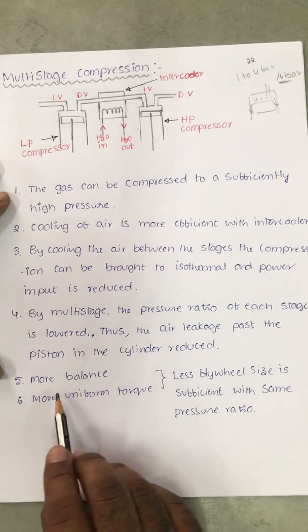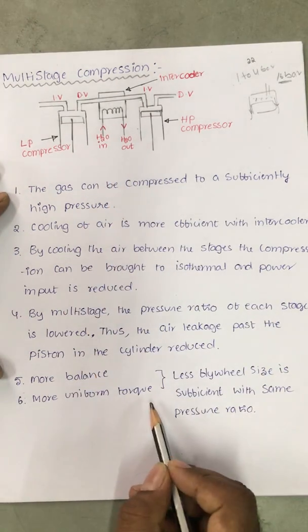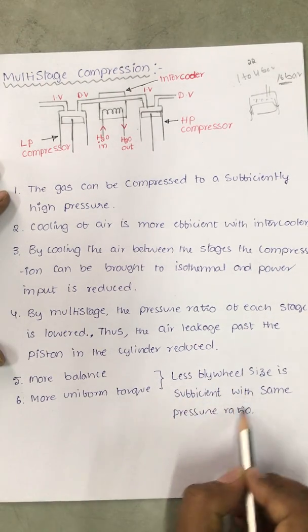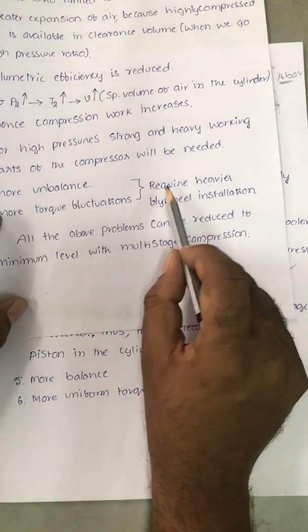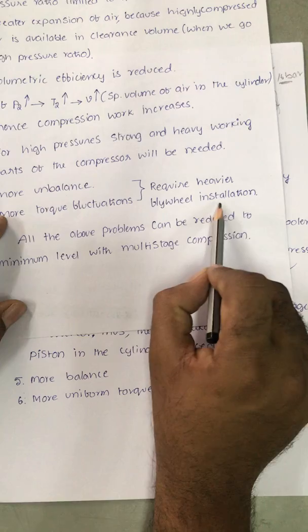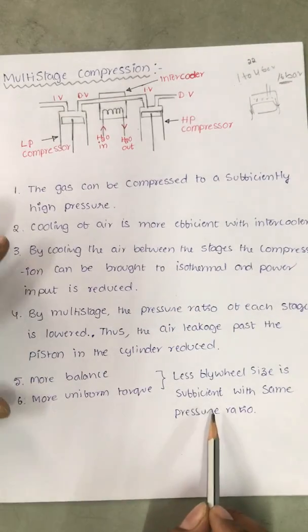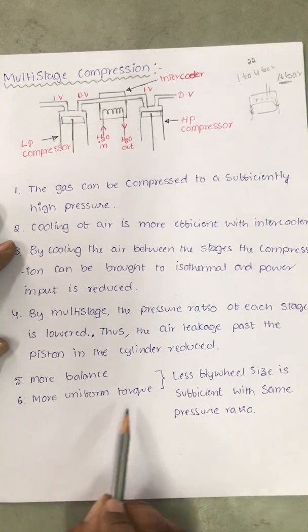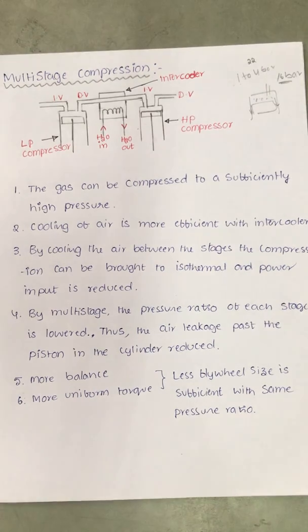Multistage compression provides more balance and more uniform torque. With more uniform torque, a smaller flywheel size is sufficient. Compared to single stage compression — which requires a larger, heavier flywheel for the same pressure ratio — multistage compression achieves better balance and uniform torque with less flywheel size. These are the key differences between single stage and multistage compression.